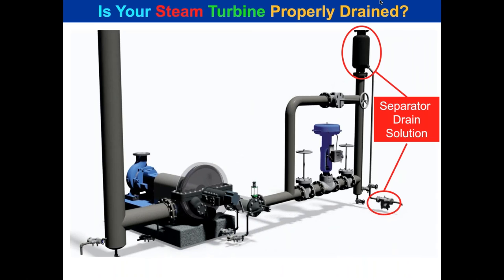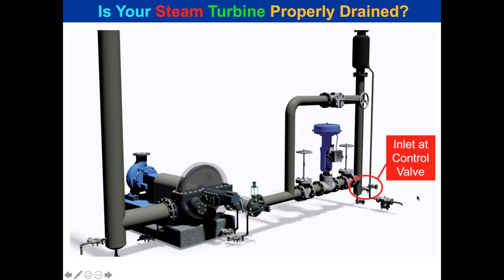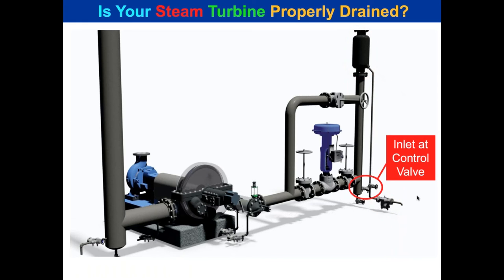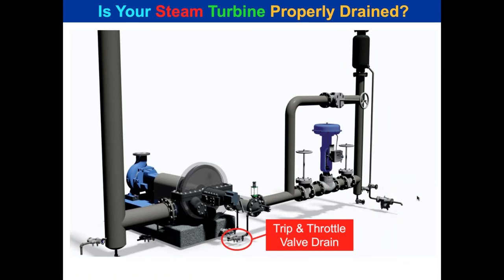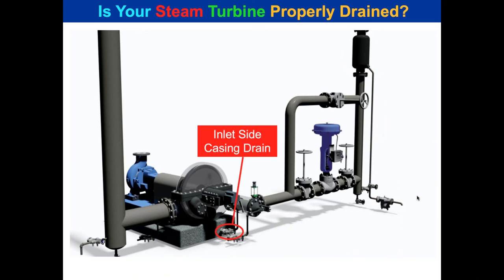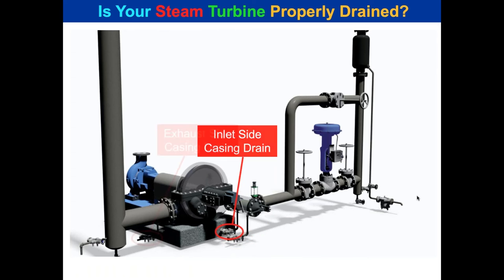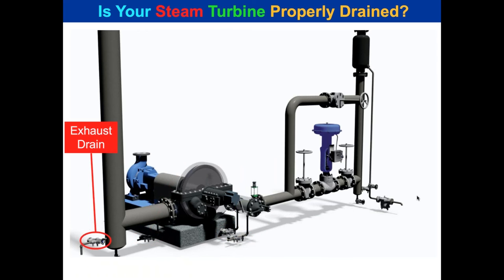We put a separator drain location with a CDL to remove already-disentrained condensate, then a separator to remove entrained condensate. The engineered separated drain solution includes an inlet trap to the control valve, a trip and throttle valve — often just plugged with no traps — casing drain on the inlet side, casing drain on the outlet side, and an exhaust drain.